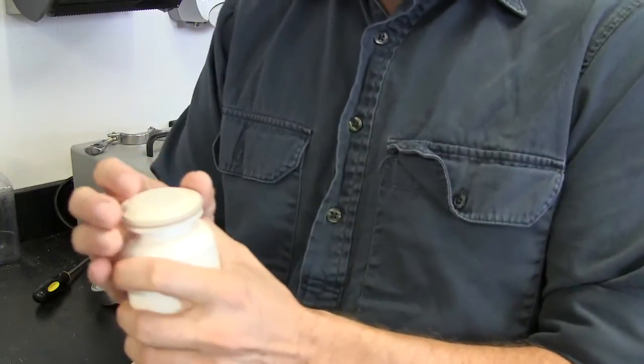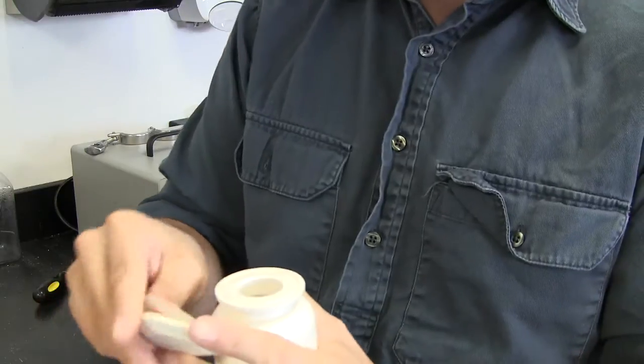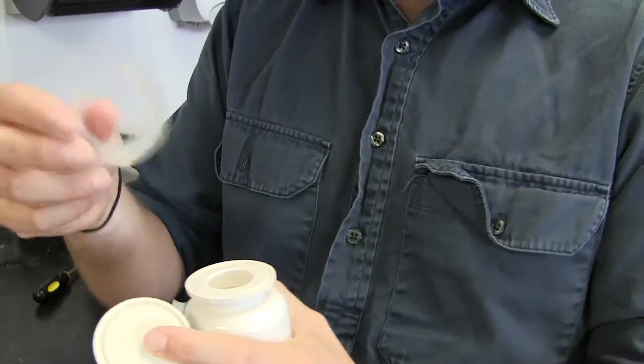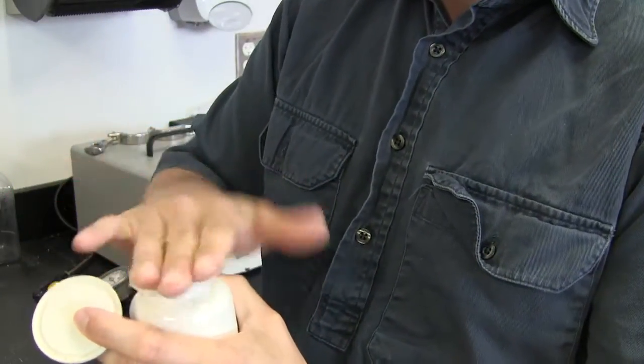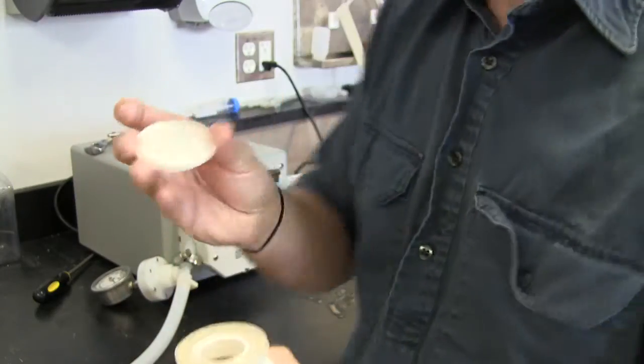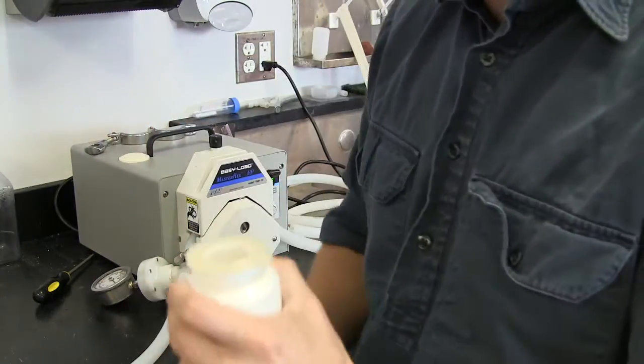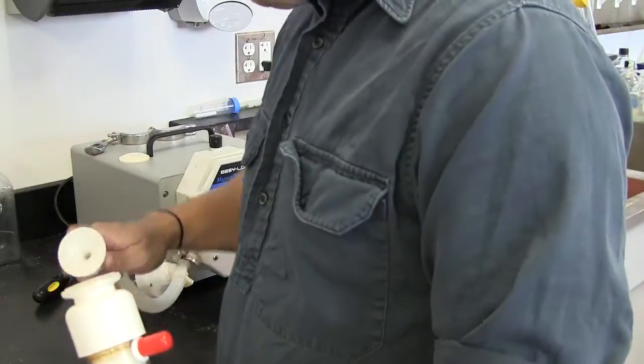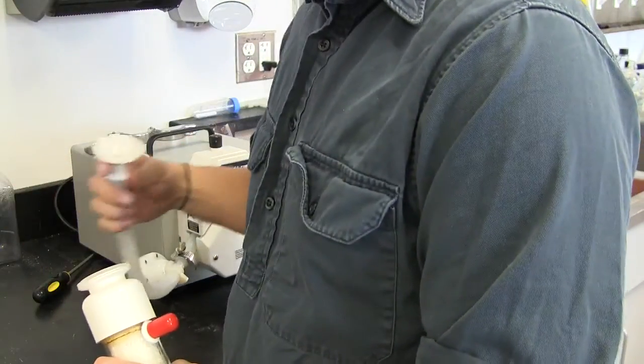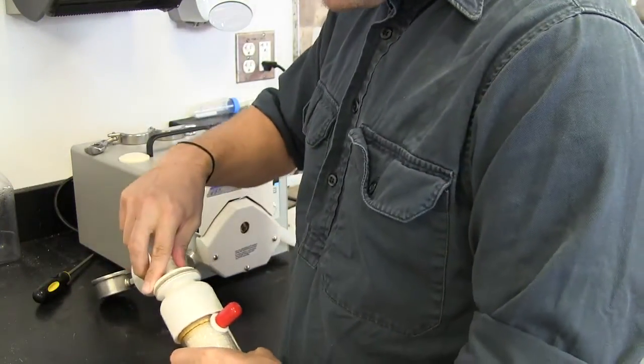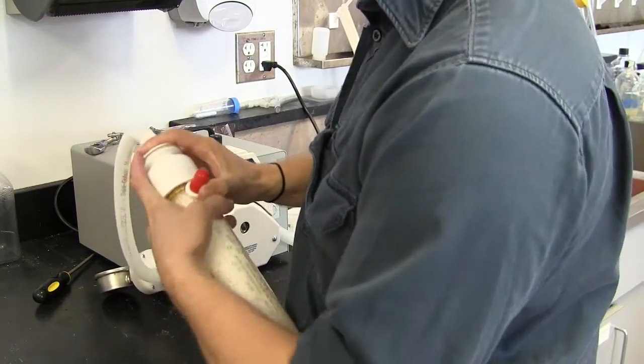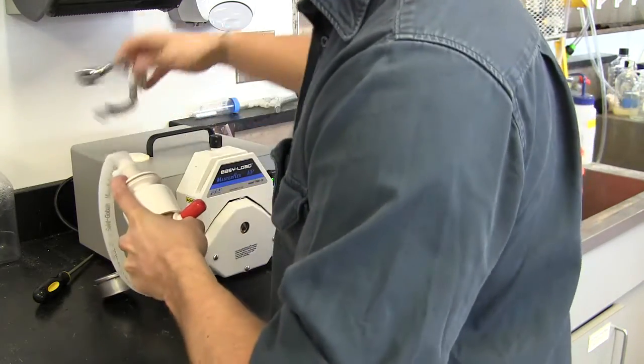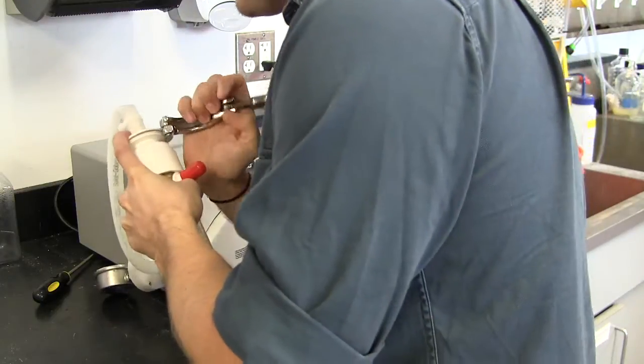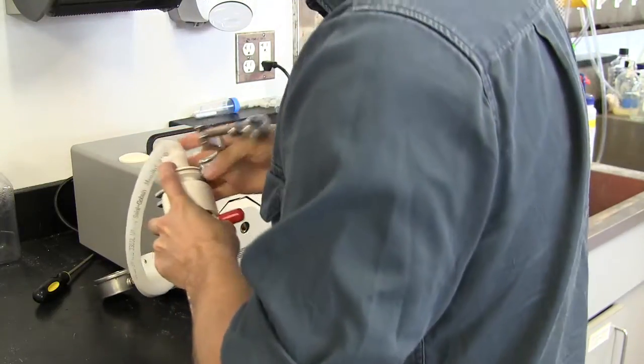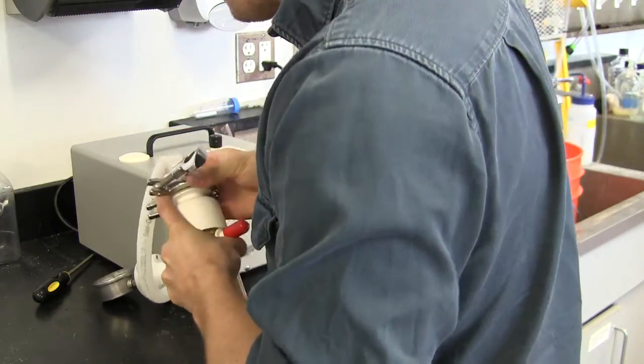Then at the end of the TFF here, you can see there's a cap and a ring, a clear sealing rubber ring. So leave that on there, take the white cap off. I also put that on top of the TFF, the peristaltic. Then what you do is you take the piece at the end of your tubing and marry it up to the end of the TFF, hold it in position, and then reattach the clamp. Alright, sometimes this gets fiddly.